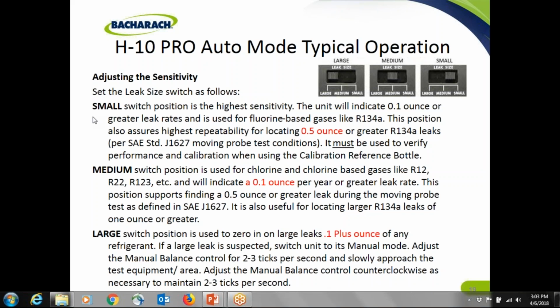This position also assures highest repeatability for locating 0.5 ounce or greater 134A leaks per SAE standard J1627, moving probe test conditions. It must be used to verify performance and calibration when you use the calibration reference bottle. So when you use that reference bottle, you want to put it in the small switch position.